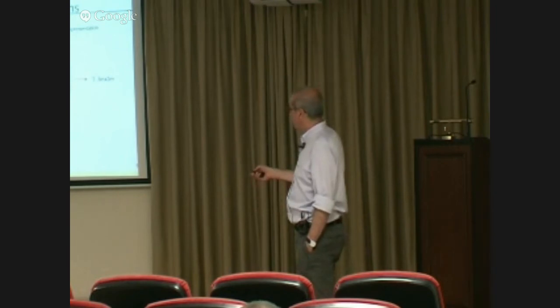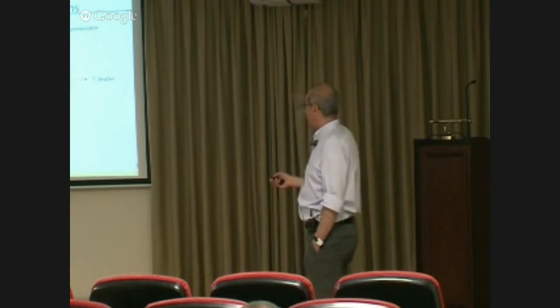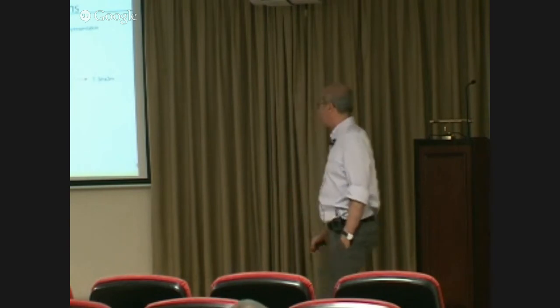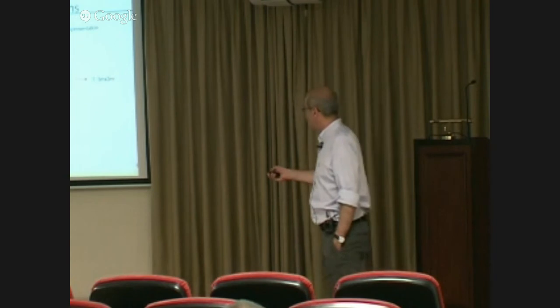These modal transformations are from fault analysis. In this case, since these are three-phase measurements, you put it into a big diagonal matrix, where each block corresponds to one measured three-phase measurement. Then applying this from the left to each item, you get this picture.